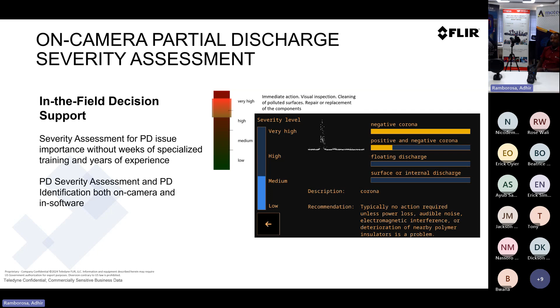Most of the questions people ask is whether the thermal imaging camera can discover what the acoustic imaging does. No, it can't. They actually supplement each other. They definitely supplement each other's work. There are some overlaps in detection, but it also depends on what type of partial discharge you have and whether it's going to heat up the component or not. That's why FLIR actually went into the acoustic space, because it's a complementary product for the same condition monitoring target market that we've got.